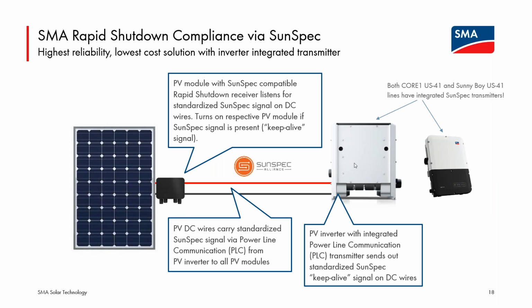Again, kind of discussing what SunSpec rapid shutdown is providing for code compliance. If you're not familiar with the SunSpec Alliance, it is an industry alliance of over 100 companies, and SMA is one of those companies. And they are kind of chartered with solving industry-wide problems. So they tackled first interoperable communication between hardware of different manufacturers. So they came up with a subset of the Modbus protocol called SunSpec Modbus. Then they moved on to solving rapid shutdown. So they produced this open standard.